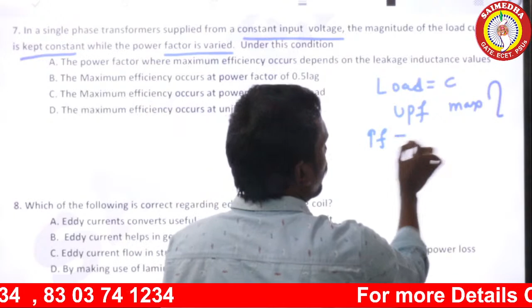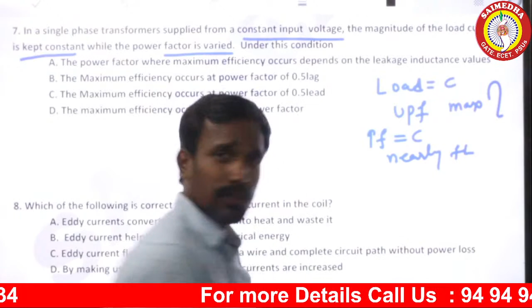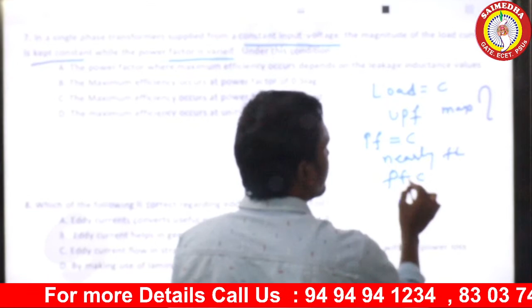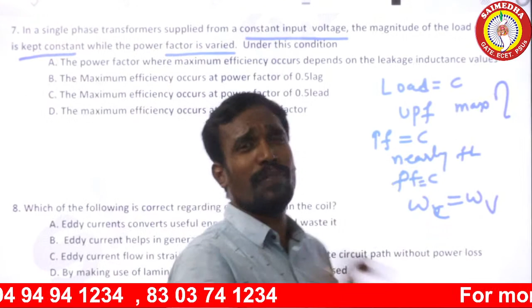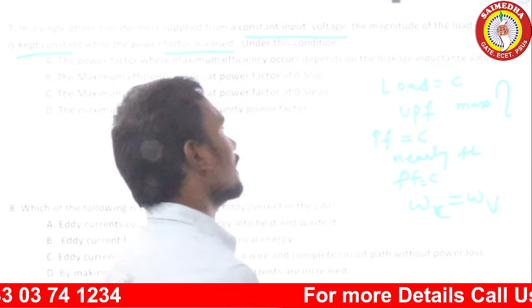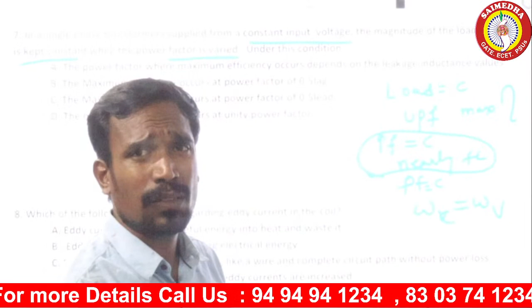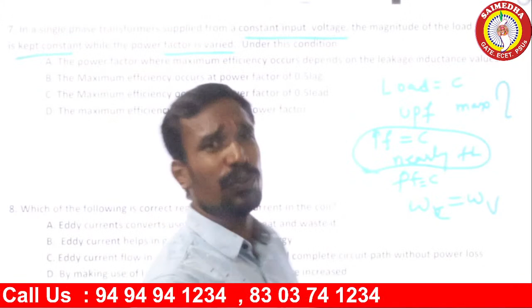When power factor is constant, maximum efficiency occurs when variable losses equal constant losses. For a power transformer this happens nearly at full load, while for a distribution transformer it happens nearly at off load. So we can get maximum efficiency at nearly full load for a power transformer and nearly half load for a distribution transformer.